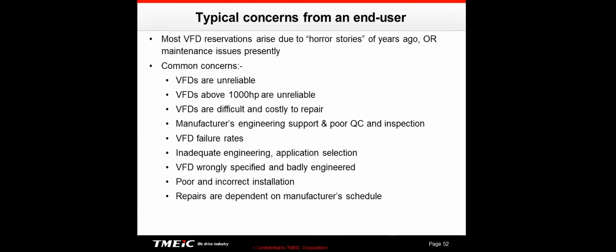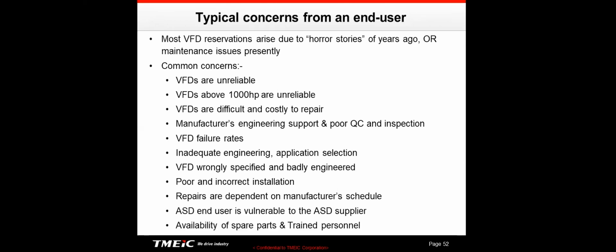They have excellent harmonics, excellent power factor, excellent waveforms to the motor that protect the motor from high voltages. And they are actually safer than a low voltage drive to work on because you are never allowed to get near the medium voltage components. In order to get to the medium voltage components, you actually have to use Kirk key interlocks to shut off all your power, so that really these things are much safer to work on than low voltage. Low voltage, you open up the door and there's 480 volts right there. That's not the case here.